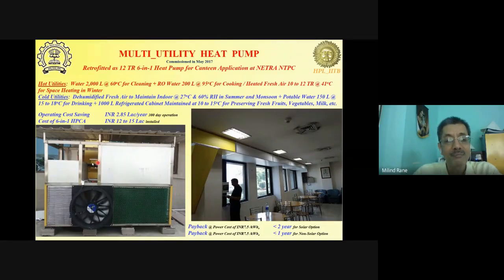So in our system, this was integrated in such a way that without any pump, we were able to deliver chilled water 24/7. For drinking purpose, you just open the tap on the chilled water outlet, and you can drink water from there, without having any pump to circulate. Overhead tank or RO water would just flow through the heat exchanger and instantly get you the water at 15 to 18 degrees centigrade, suitable for drinking. For cleaning purpose, you just open the tap in the cleaning basin, and the overhead tank water would just enter the heat exchanger. And there was a 1,650 liter storage tank here for hot water for heat storage, and another 330 liter storage here for storing the cooling effect.